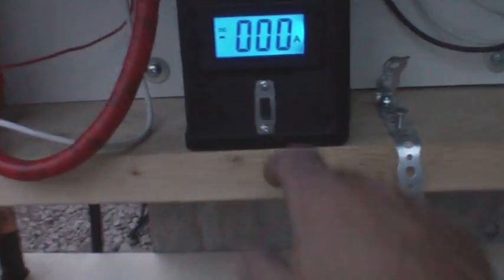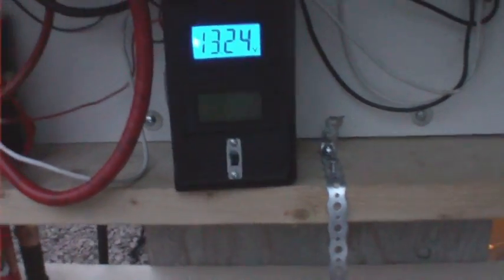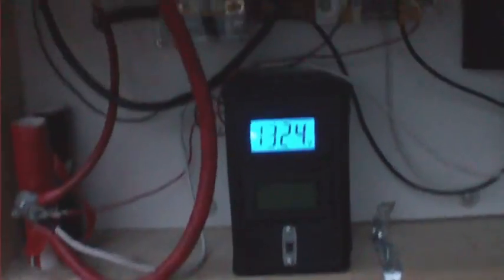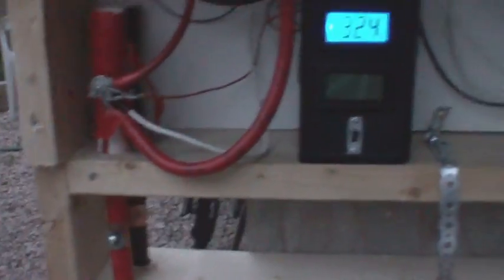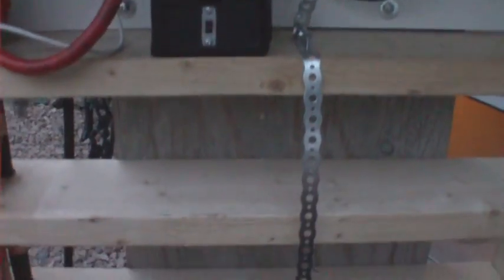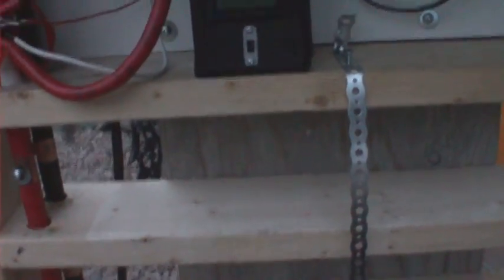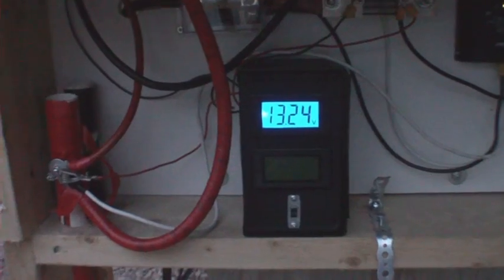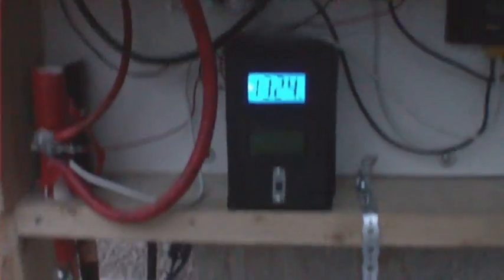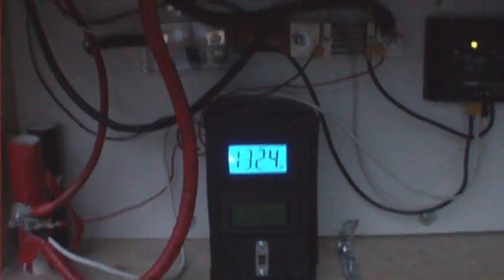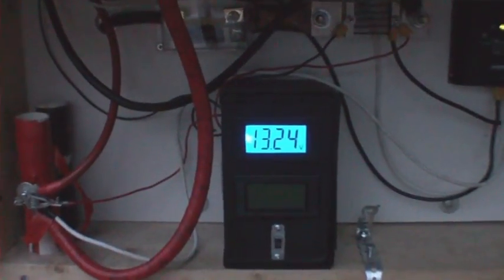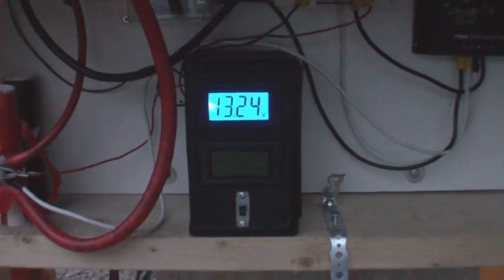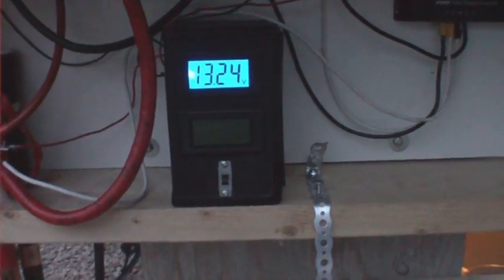Just in a little recipe box and then I just screwed the recipe box to the back wall. And I have the ammeter on a switch, mainly because it's on that 9 volt battery. And I want this set up like this because these batteries can only handle so much. I'd like to reduce that 100 amp fuse down to maybe 50 or 60 amps because these batteries can't produce, I don't want to see her producing more than 600 watts. And quite frankly, a lot of people don't really know about the draw on appliances. So this was very visual. Her house being a straw bale with minimal windows is very dark too. So she can just look up and see where her battery voltage is at and see what her draw on her bank is at and that sort of thing.